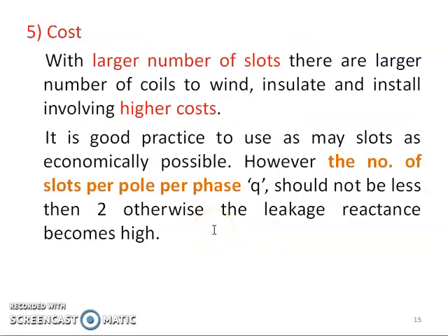Next, coming to cost factor. With a large number of slots, there are a large number of coils to wind, insulate and install. This involves higher cost, even labor cost also. If the designer chooses a large number of slots, then based on the number of slots, more coils need to be put, more slots need to be insulated, and with more slots, the installation cost also increases. Hence, overall cost will increase due to the large number of slots.